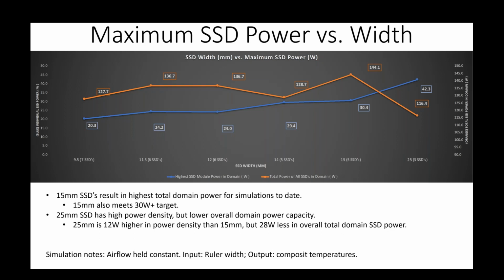So your pressure curve is going to be totally reliant on how many rulers you have in that device, agnostic of what components you have downstream. And that's what you should measure to. If Intel or Western Digital say you need 150, or let's say 70 LFM through a device, and you put it in your system and you're only getting 60 LFM because you have a bunch of cabling behind your ruler cage, then that's up to the system designer to optimize to meet the power requirements of the module, not the device supplier. Yes, agreed.